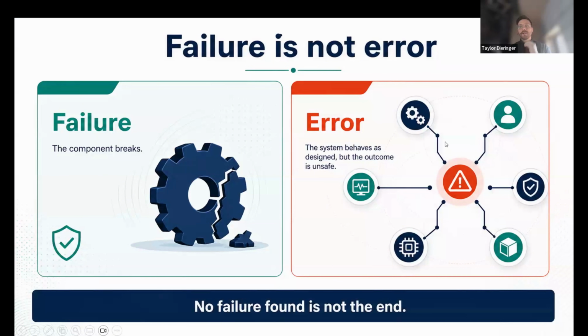All right, so we're going to walk through the typical structure of risk management files and why they fail in post-market surveillance so often. This first point here, failure is not the same as error, right? If we have individual sequences of events identified as our risk management line items, what can happen is we have a very siloed look at how hazardous situations can occur. ISO 14971 requires us to look at how hazardous situations can occur from both normal use and fault conditions. If we only have failure mode effect analyses and sequences of events defining our risk management line items, then we're missing a big side of what risk management means.